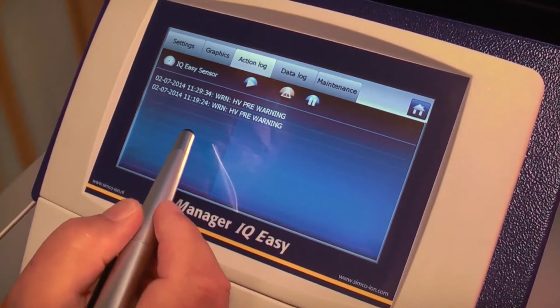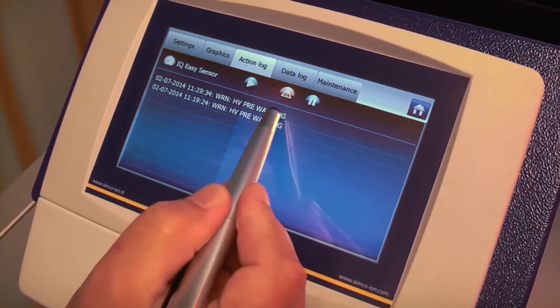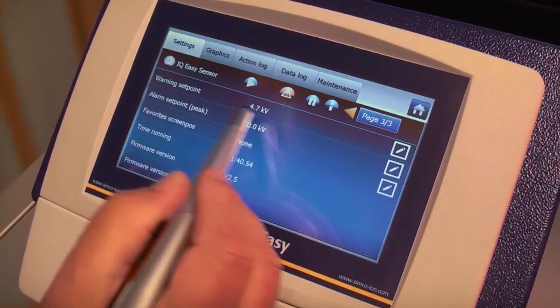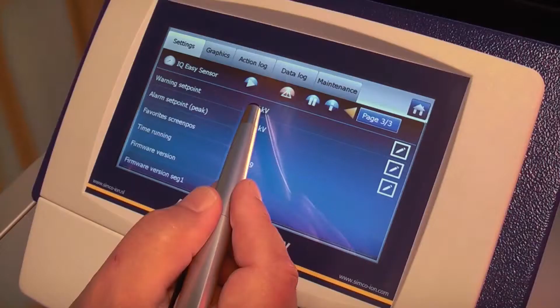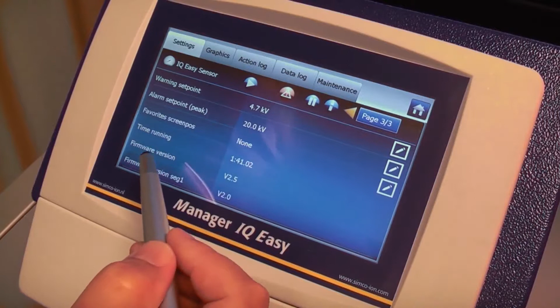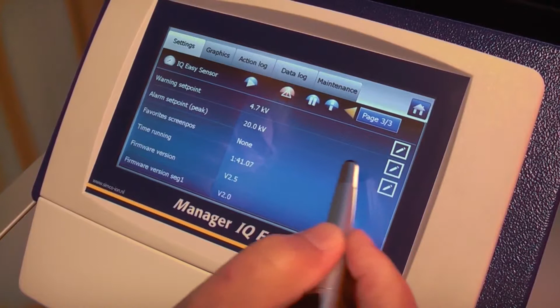When I want to know what the warning is, I go into the action log and look at the warning. And it says, okay, high voltage, there is a pre-warning, which means it's giving me a warning because the voltage that has been measured on the web is above 4.7 kilovolts. I can do the same for the alarm set point. It is now at 20 kilovolts.